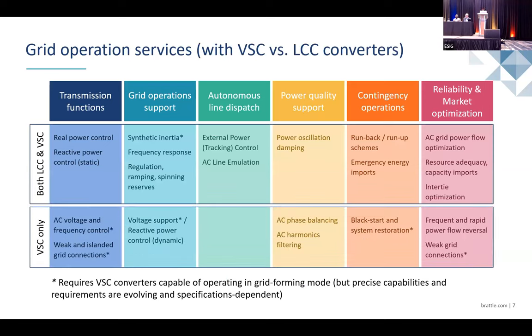And these are some of the functionalities of HVDC converters. To start with, highlighted in blue, the main functionality of HVDC is power transmission, and you can get that from both LCC and VSC. At the same time, you can also control reactive power output from LCC and VSC converters. And with VSC, more than just real power and reactive power, we can also do a bit more. Probably I'll go to the next one. We'll come back to that.